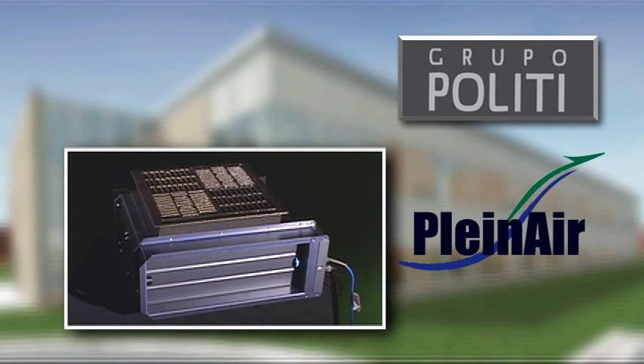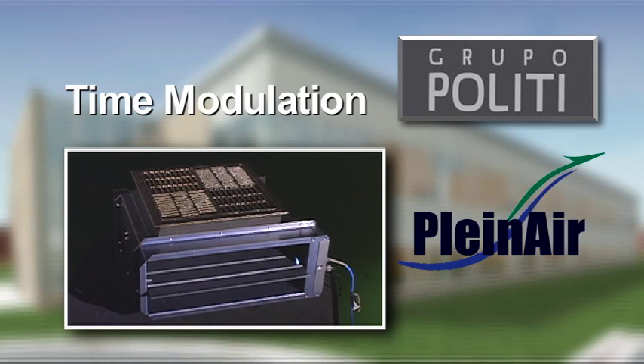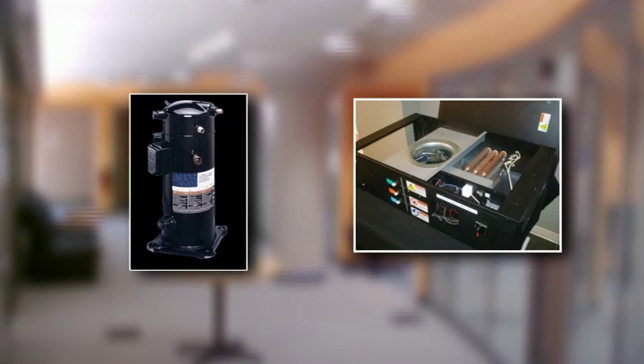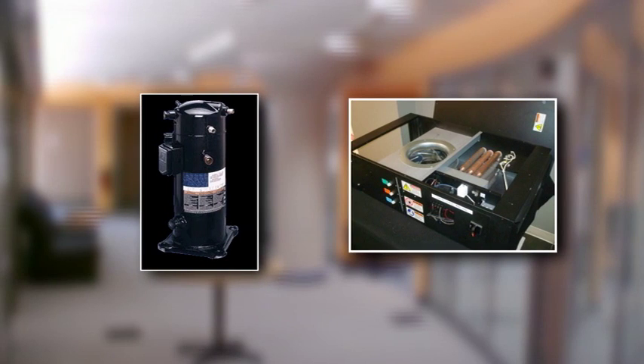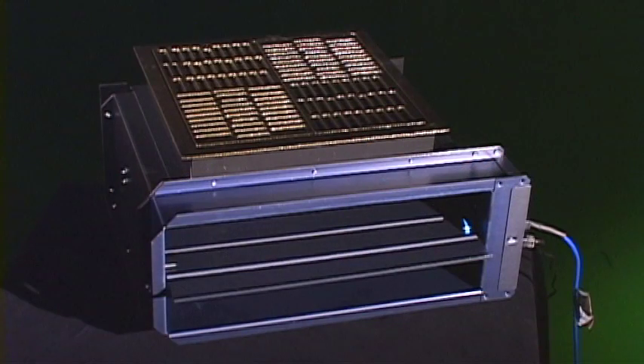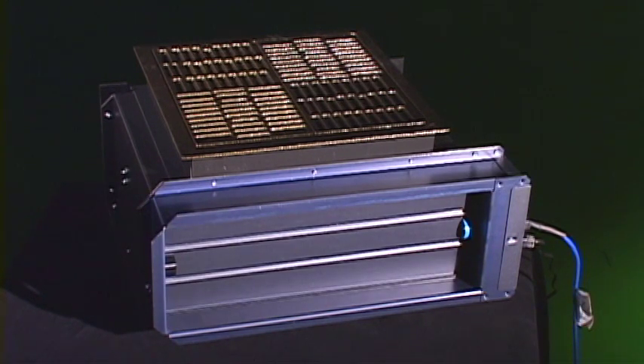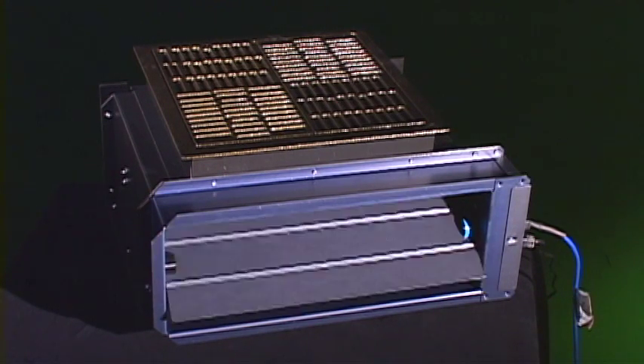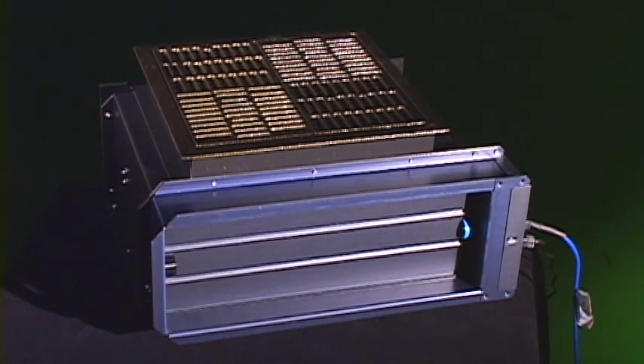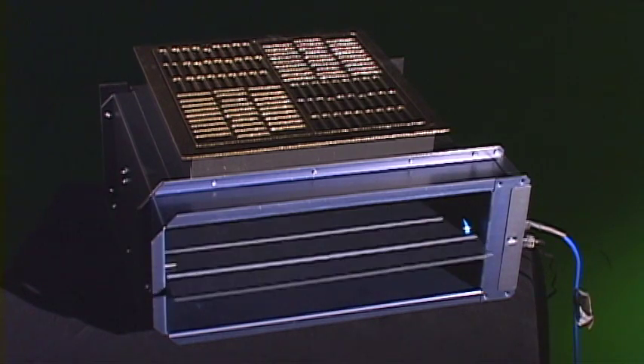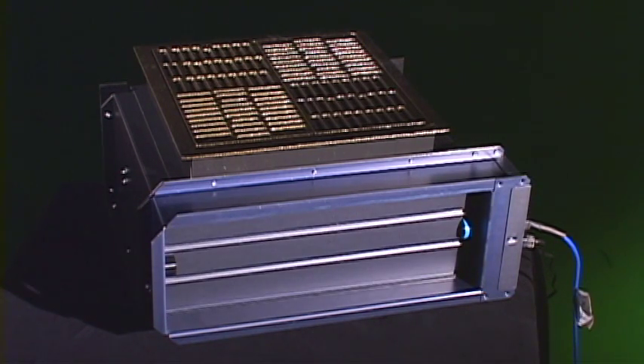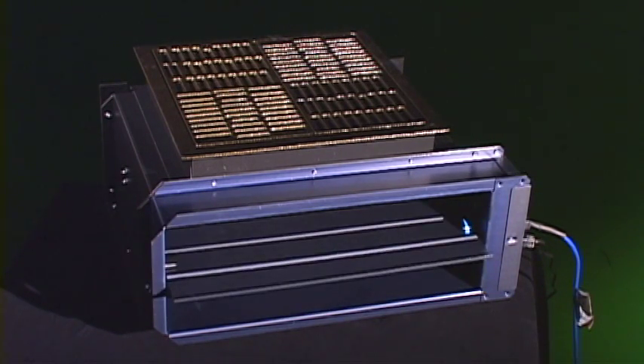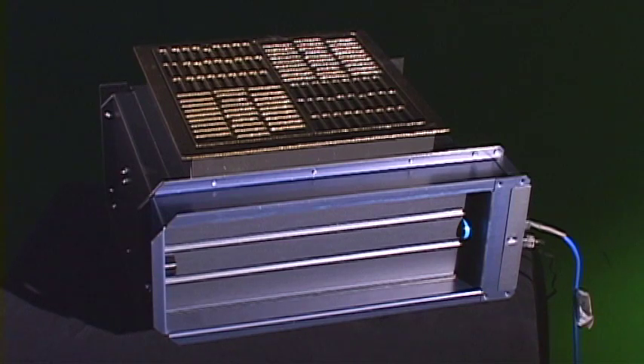PleinAIr has developed a better way with the introduction of the time modulation process. This concept has already been successfully applied in compressor modulation and heating control systems. Instead of throttling the air like a VAV box, the air valve has only 2 positions, open or closed. To achieve 50% load, the valve is open for 6 seconds and then closed for 6 seconds. To achieve 33% load, the valve is open for 6 seconds, then closed for 12 seconds.